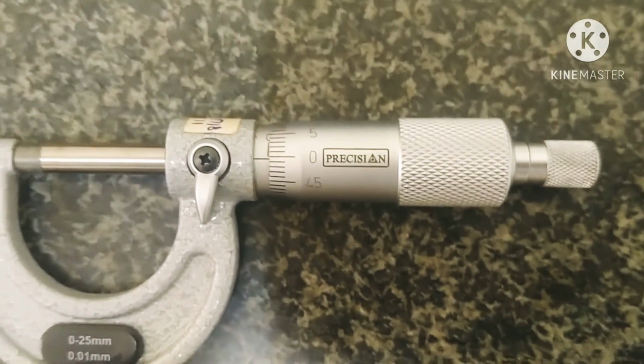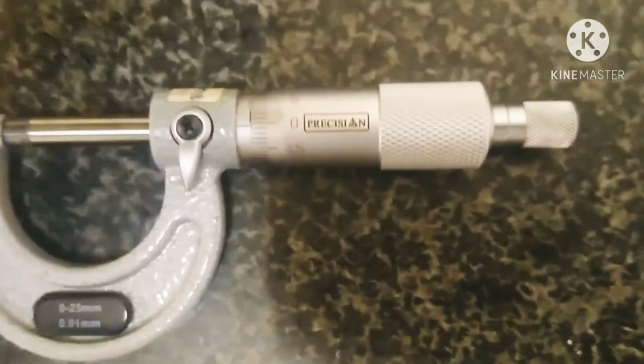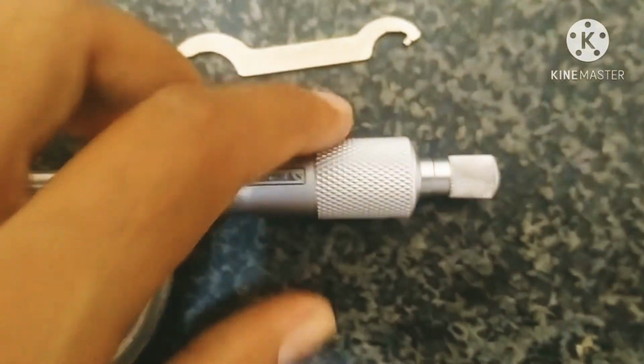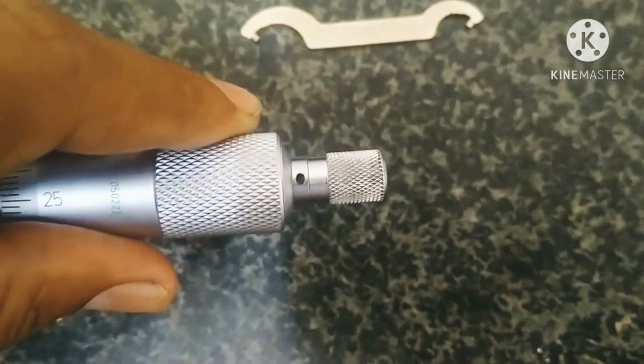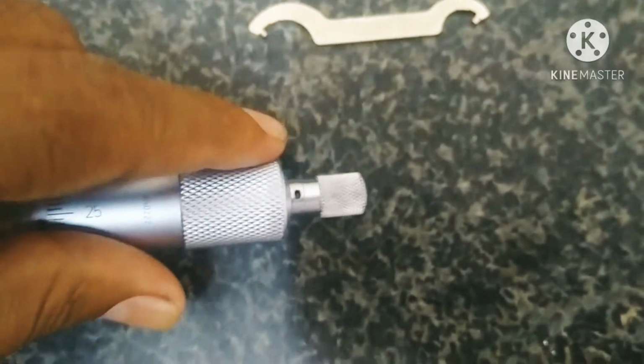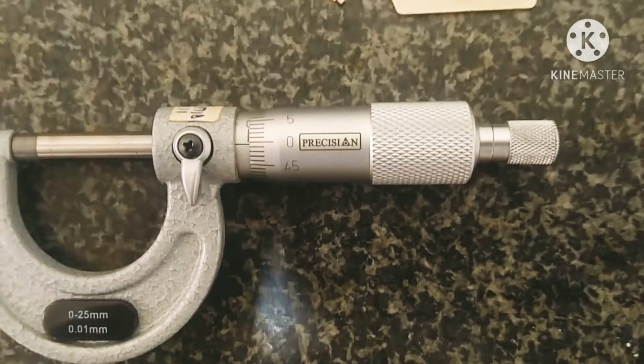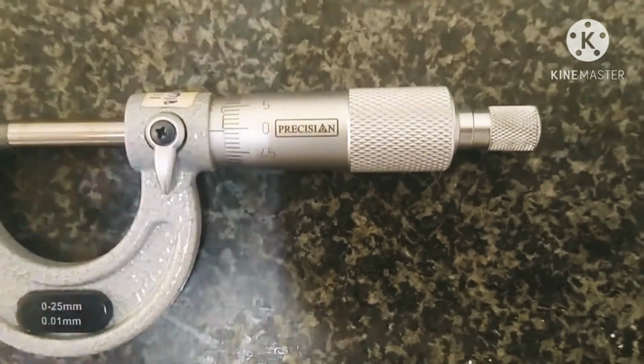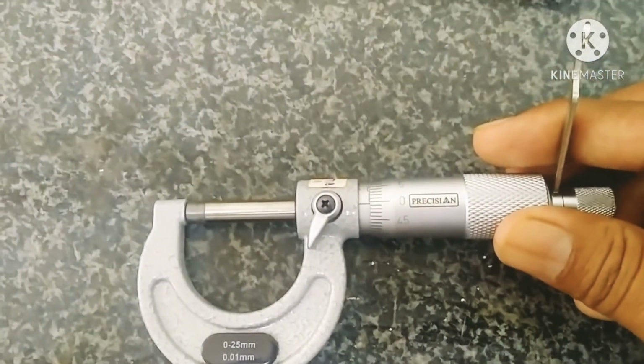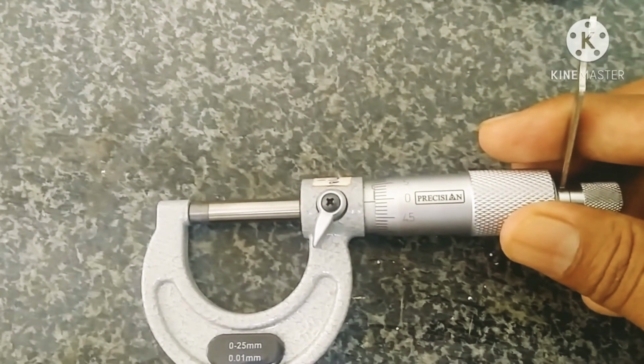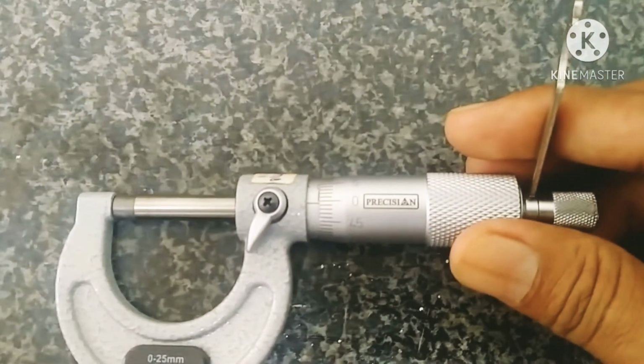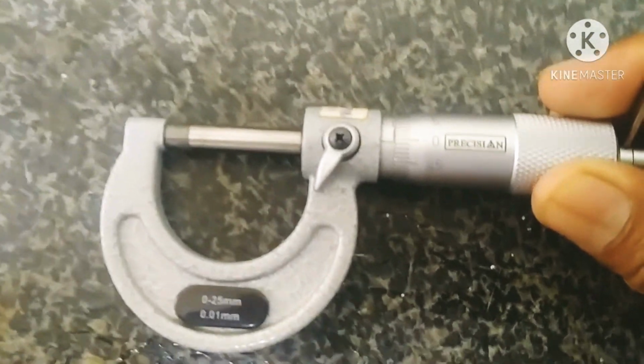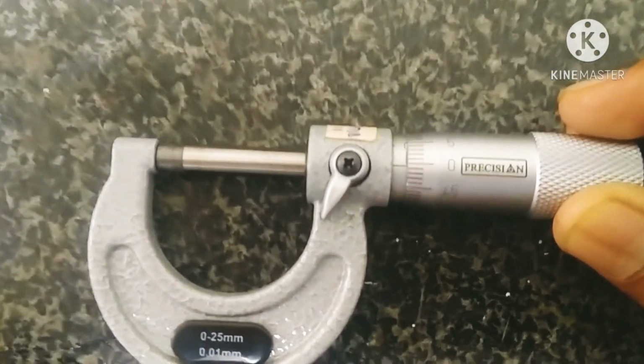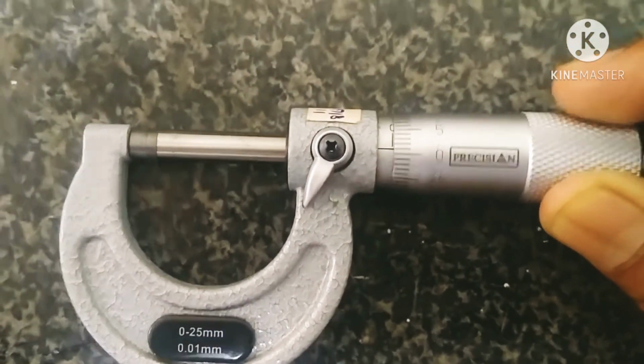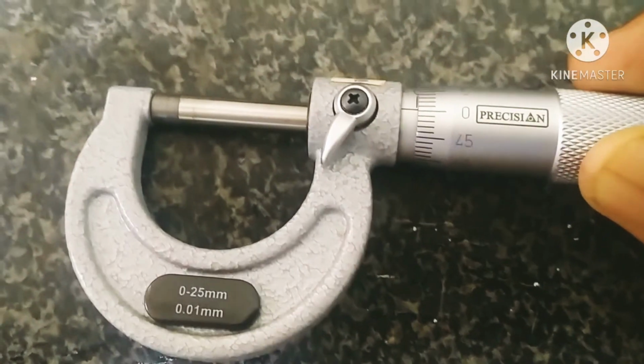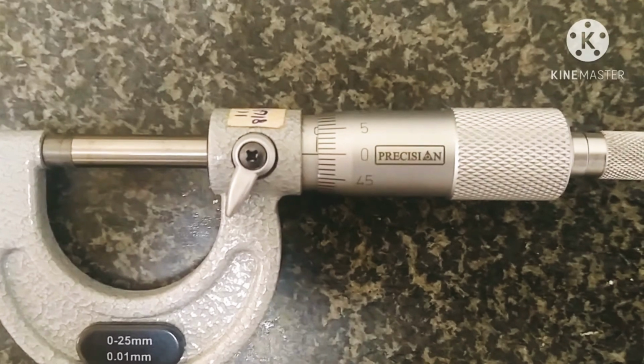We can do the adjustment by adjusting the barrel to zero with the help of a pin, which is provided with the micrometer. You can see a slot is provided, and with the help of this pin we can adjust the barrel to zero. It is ahead of zero, so we need to rotate it in the anti-clockwise direction. Now with the help of this pin I am adjusting the barrel to the zero of the thimble. You can see I am moving it. Now with the help of the pin I have set it to 0.